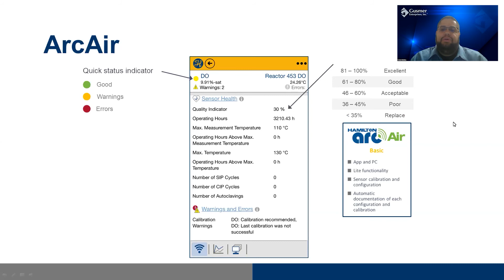Again, the software is used to calibrate the sensor. It's really user friendly and intuitive. Here's a slide that shows you what you might see on the software on your phone. So in the upper left-hand corner, it shows you what sensor you're using, what the current warning messages say, what the current value is right there, 9.91%. You can change the readout from percent to ppm to ppb. Right there, it shows you in the upper right-hand corner what the sensor name is.